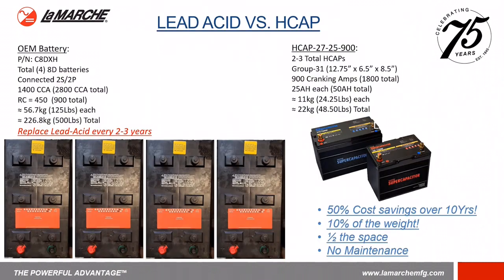So at the end, the customer saved or will be saving over 50% over a 10-year period. Again, total cost of ownership was one of their big objectives there. They wanted to make sure they reduce cost over a 10-year period. So instead of replacing batteries every 2 to 3 years and having their generator supplier dealer do this servicing, they were able to go ahead and start doing their own servicing, basically, just monitor checking the connections on the HCAP.